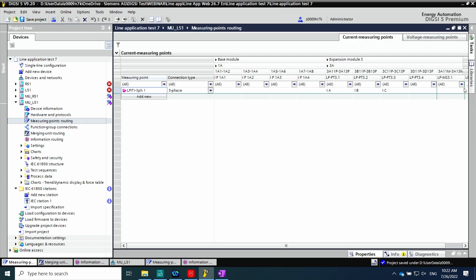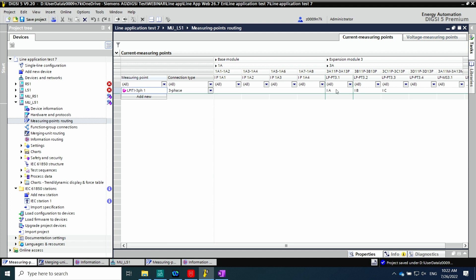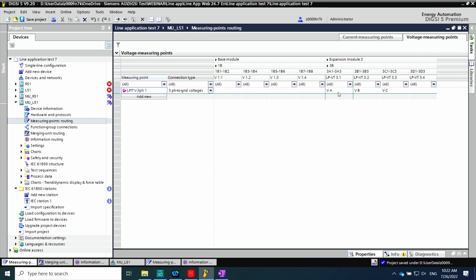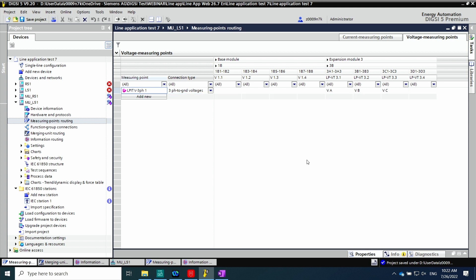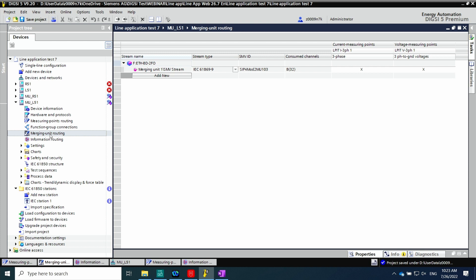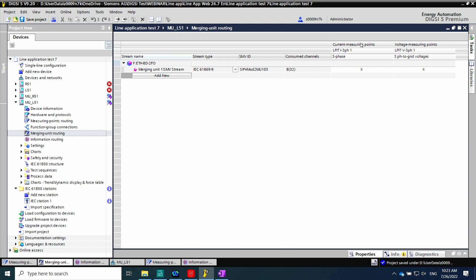After that, I go to measuring points routing. Here we have the current measuring points and voltage measuring points. In expansion module 3, we can see the currents coming from the LPITs: phase A, B, and C for current, as well as the voltage measuring points from the voltage divider for phases A, B, and C. Now that this information is available in the measuring points, the merging unit can transmit it using the process bus network. In the merging unit routing, we can assign these measuring points to be transferred using sampled measured values — the current and voltage measuring points coming from the LPIT.